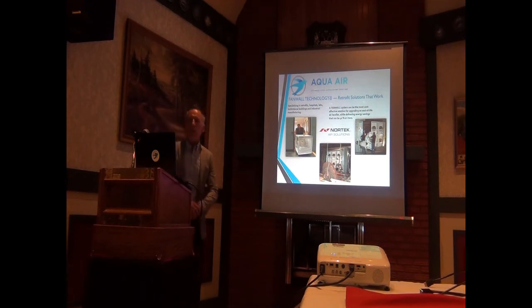Fan wall technology, how has it helped with retrofits? Well, if you've all been in buildings, the mechanical rooms and the HVAC equipment are often buried deep down in the basements, high up in the upper floors, or even if it's on the main floor, like in the older schools we've been in, they built the building around the HVAC or the mechanical room. So with that said, even if it is on the main floor, 25, 30 years ago plus, they weren't thinking much about how to replace this equipment or how to improve the current system that I have.